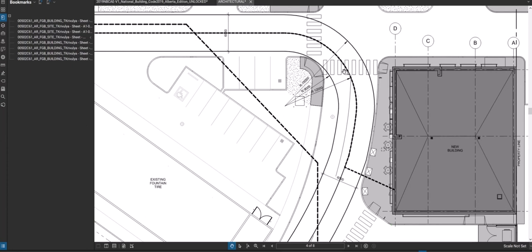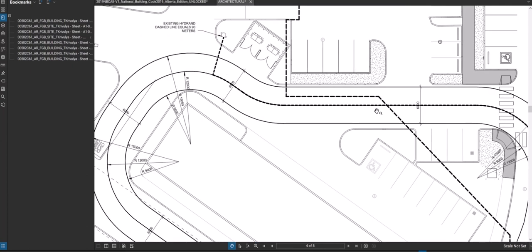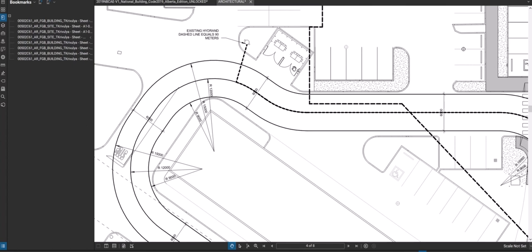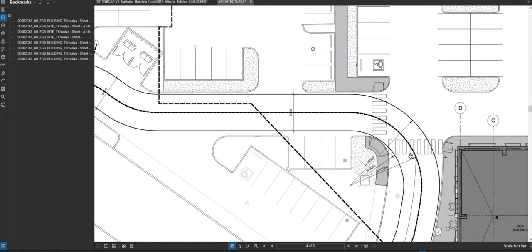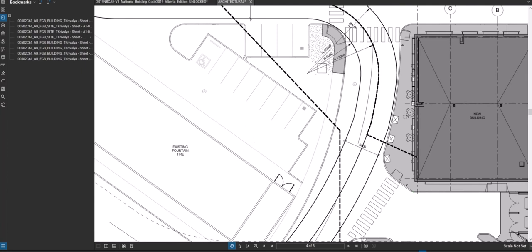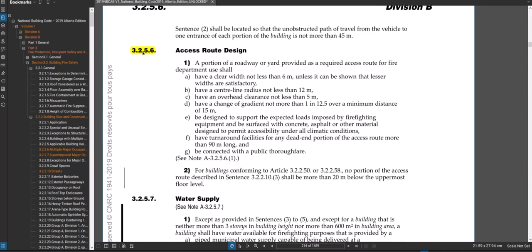Here's an example of a fire truck access plan showing that six-meter width and the 12-meter radius — the outside radius is 15 meters and the inside is 9 meters — ensuring the truck can get to the principal entry and back out. In this case there was no fire department connection, so referencing the earlier article, the fire hydrant can't be more than 90 meters away. There's an existing hydrant with a dashed line along the path to the principal entry, and that line must be less than 90 meters or a new hydrant would need to be installed.